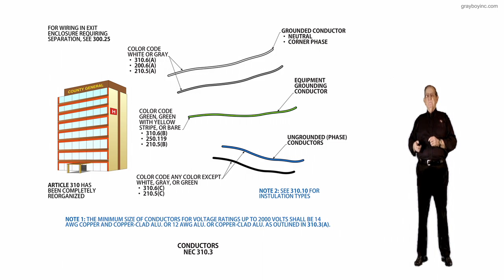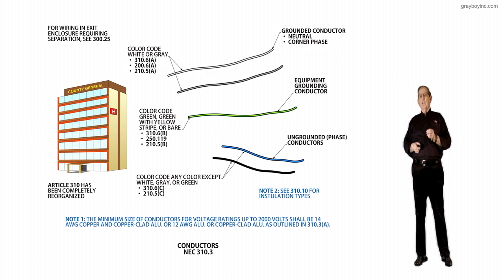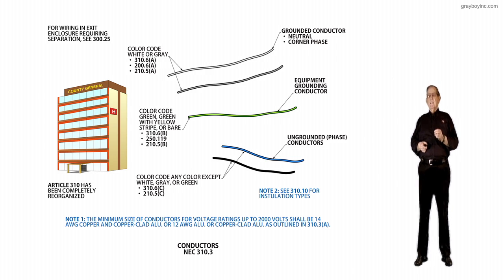The note one now tells you that the minimum size of conductors for voltage ratings up to 2,000 volts should be number 14 AWG copper and copper clad aluminum or number 12 for aluminum or copper clad aluminum as outlined in 310.3A. They're giving you the specific requirements here so that we don't make mistakes. And the note two says if you want to know how to use this insulation, go to 310.10 and it will tell you exactly the type of insulation you would have to use in damp, dry or wet locations or exposed to the sun.